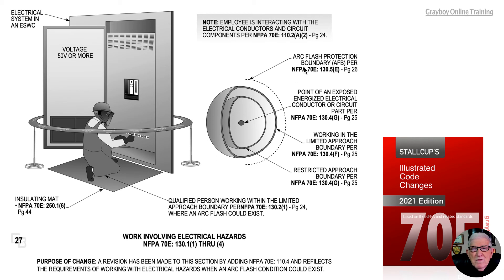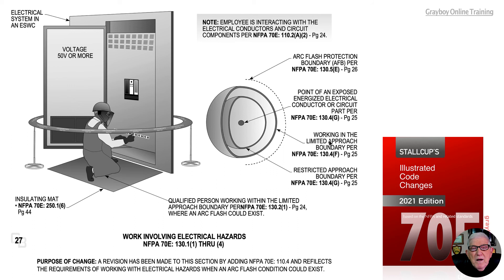As stated previously, 70E 130.5E on page 26: when you're crossing that arc flash boundary, you need your PPE on to protect you for the particular job task. The limited approach boundary seen here in 130.4F is where you want to watch for shock, making sure you're protected from shock conditions.